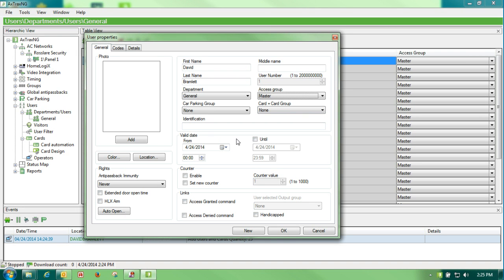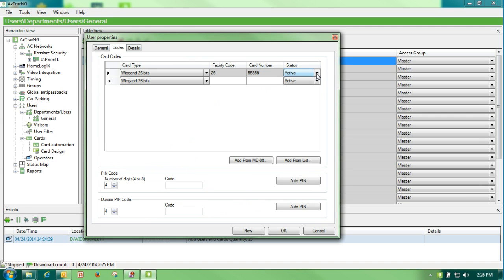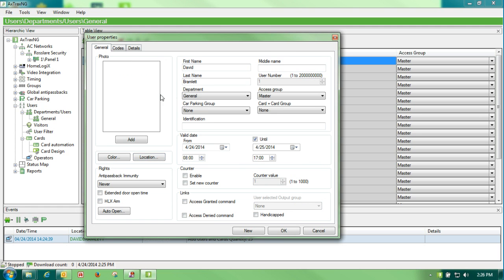The valid date, if this is checked, the valid date would be used for subcontractors. I have a subcontractor coming in that is going to work for two days. I would check my valid date and I would start it at 0800 and I would end it at 1700 on Friday tomorrow. And with this checked, the badge card pin number would be good until this time. At that time frame, the card would be turned to inactive and that badge would not be able to be used from that time until there was some manual intervention done.